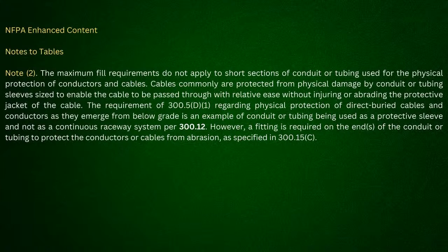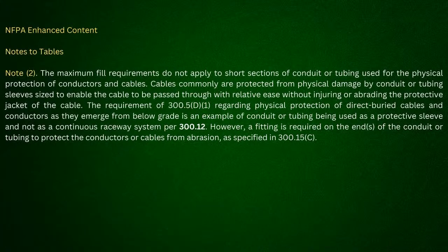Matter of fact, if you look at the enhanced content from NFPA, they do not call it a raceway sleeve. They just say it's a sleeve. So this one's interesting because Weedman says if you have flexible metallic conduit, can you run it in a wet location if it's less than 24 inches? Because we're just ignoring Chapter 3. Well, this is where you go with the listing and labeling and the manufacturer instructions, and they do not permit that to be run in a wet location. So it has nothing to do with the code.